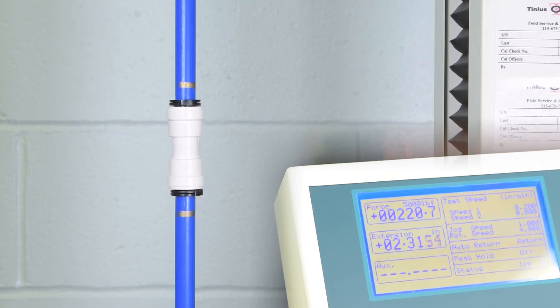So we're close to 220 pounds of force and the fitting is still holding. Right now the PEX pipe is stretching and deforming while the fitting is still gripping.